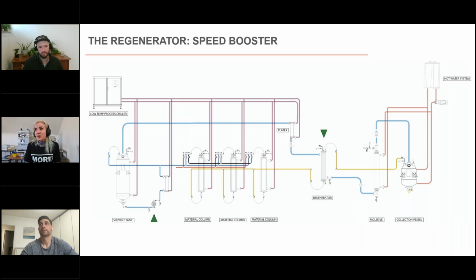I'm going to say this is the perfect opportunity to stop overfilling your columns as well. One of the most common reasons that you would have a lot of extra solvent in your column at the end of a run is your inability to recover quickly and to recover all of it. When you think about a recovery pump, it's a push pull, so every time it pulls, things are moving, and then when it stops pulling, things move back just slightly. And so you end up with this ebb and flow at the bottom of your column going towards wherever it needs to go. And that's not good.